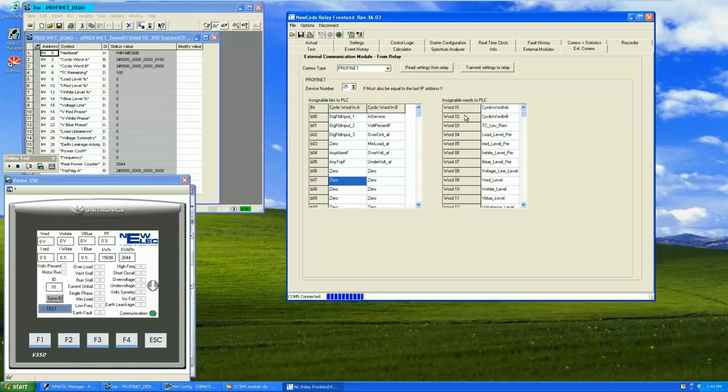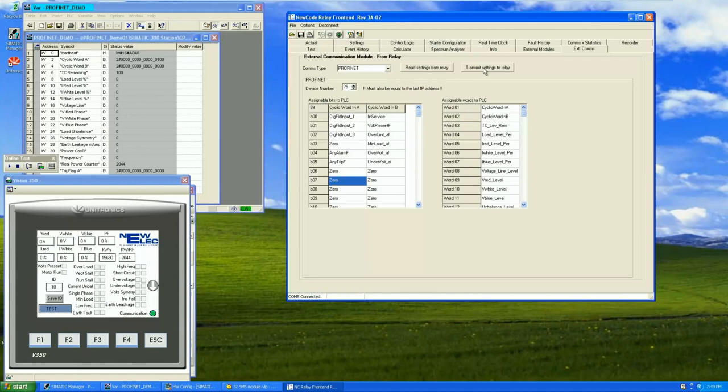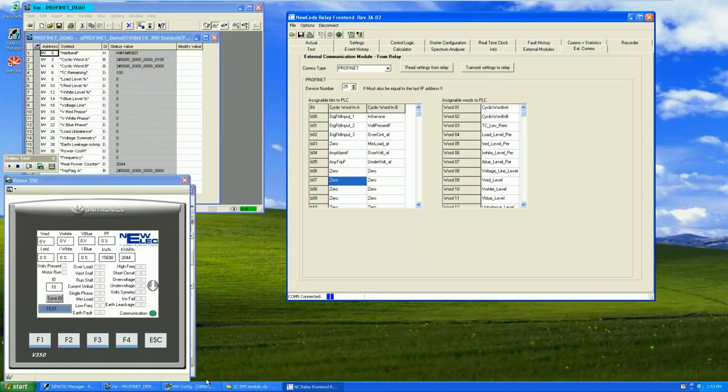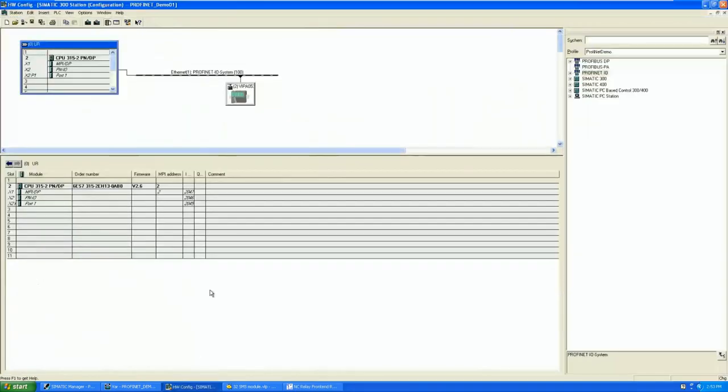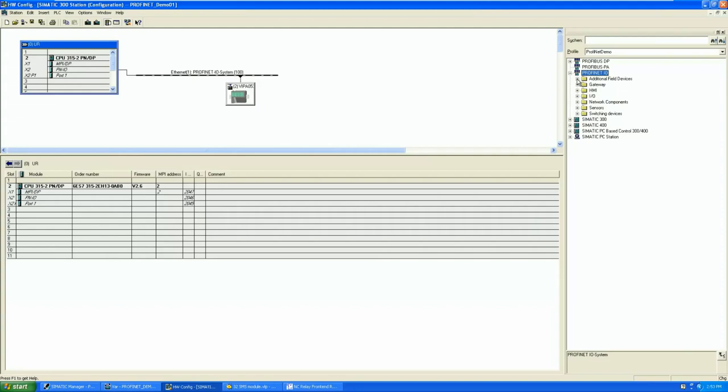On the left side is two words and in these words the bits can be fully customized as what the system integrator requires. On the right hand side we've got assignable words from 1 to 20. These are also fully customizable as what the system integrator needs these words to be. These words will travel from the NewCode to the PLC. After the configuration is done, this configuration can be transmitted to the NewCode relay. The PROFINET module will accept these settings and go into data exchange if the PLC is configured correctly.